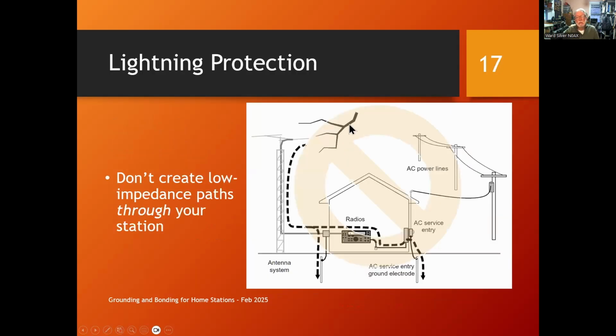So what happens if you don't have everything bonded together? All right, here's the lightning, and you've got a tower and some feed lines, and you've got an entry panel, and it's got a ground rod. Sure, that's great. It's also connected through the panels to your radios, and they're powered from this branch circuit, and you've got your AC service entry over here, and it's got its own ground rod. Well, these aren't connected together, so here comes the lightning, and it flows along here, and it says, oh, look here. Well, there's a pretty good ground connection over here, but by golly, there's also a fairly low impedance path that goes over here to this ground rod.